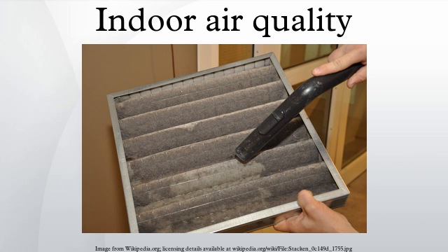Moisture management and humidity control requires operating HVAC systems as designed. Moisture management and humidity control may conflict with efforts to optimize the operation to conserve energy. For example, moisture management and humidity control requires systems to be set to supply makeup air at lower temperatures, instead of a higher temperature sometimes used to conserve energy in cooling-dominated climate conditions. However, for most of the US and many parts of Europe and Japan, during the majority of hours of the year, outdoor air temperatures are cool enough that the air does not need further cooling to provide thermal comfort indoors.